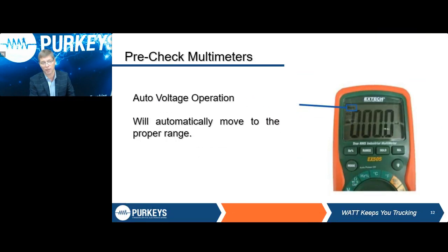The other thing, you always want to make sure you're familiar with your meter. That's why whenever we do in-person meter classes, I always tell people to bring their own meter. Why? Because we go through it and say, hey, this is where the function is on yours, or this is what yours means. The other thing, you got to make sure what type of meter you have. Most anything that's digital anymore is an automatic ranging meter. What does that mean? It's going to move the decimal, put it in the best spot to give you the most accurate reading every single time.